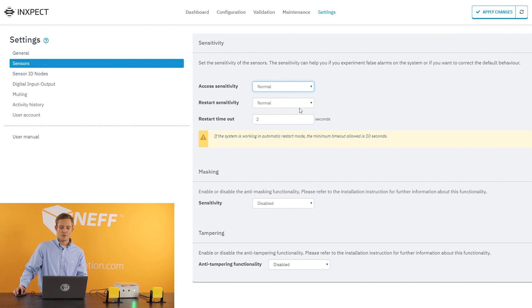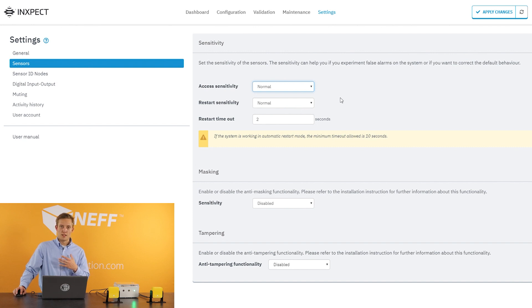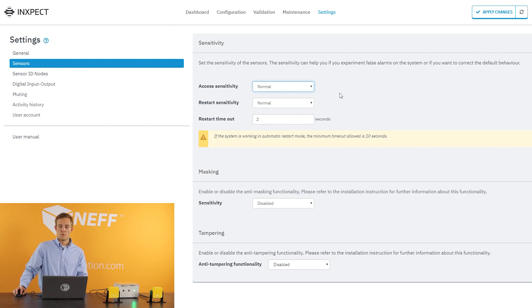Very high is a good setting for restart prevention because you can actually sense people's chest coming in and out if someone was knocked unconscious. The sensor's sensitivity would be high enough where you can actually sense that movement.